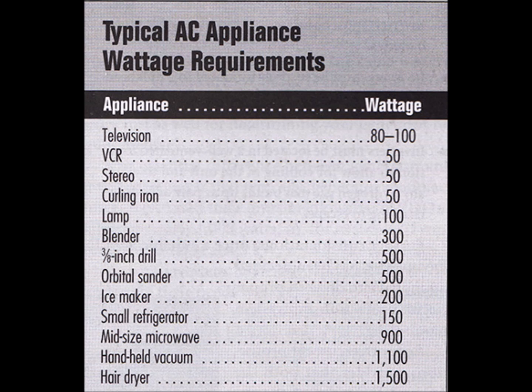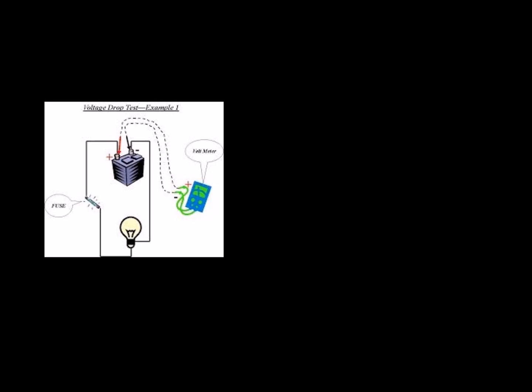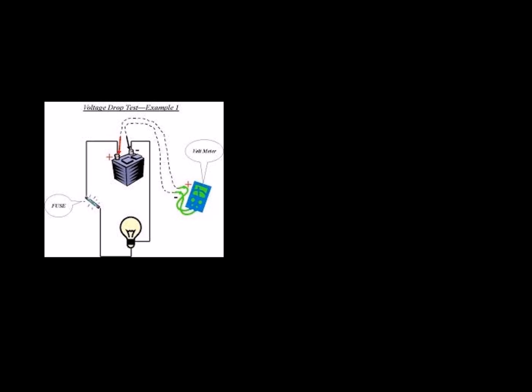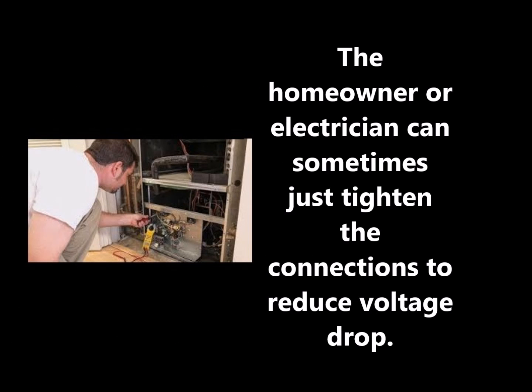It compares the voltage measurement at full load with a measurement at no load and calculates the voltage drop. The National Electric Code recommends that the combined voltage drop of the electrical system, branch circuit, and feeders not exceed 5% for optimum efficiency. It is important to note that this is a recommendation, and that local inspectors or other governing bodies may use their own judgment for an acceptable level of voltage drop for the electrical system.